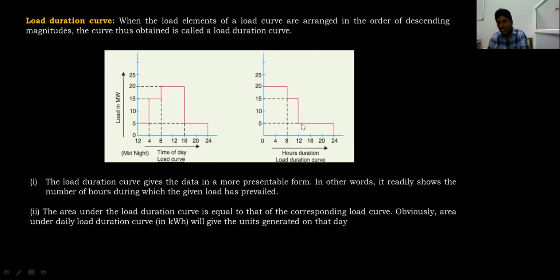In the same way, in descending order, we need to plot the maximum loads on the power station, which gives you a readable form for the operator. Easily he can understand what is the maximum load on the power station and for how much time it stands. We are converting everything into readable form, but the area under the curve remains the same. So even if you are given a load duration curve, the number of units generated per day is the same as the load curve. We can define average demand as well as maximum demand. Everything we can get from the load duration curve. But we have rearranged the load durations in such a way that the maximum demand of the power station is plotted first, and the next in descending order in the next range.